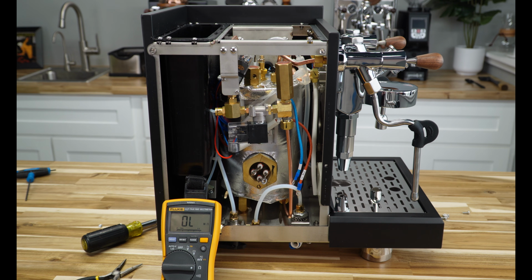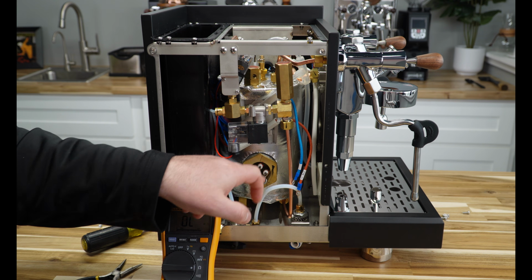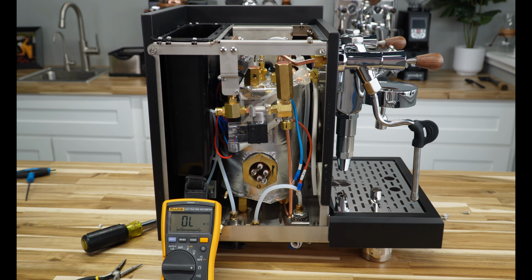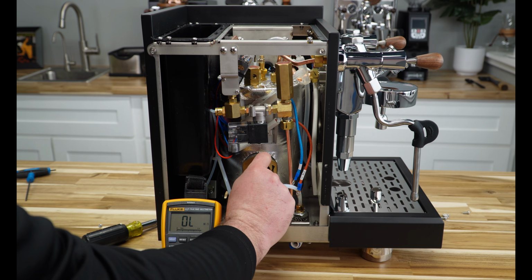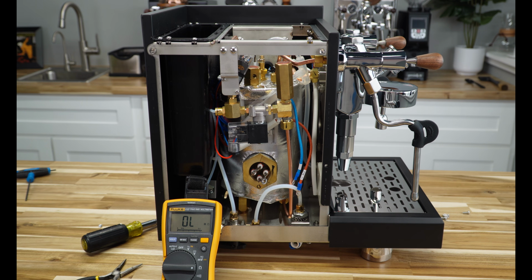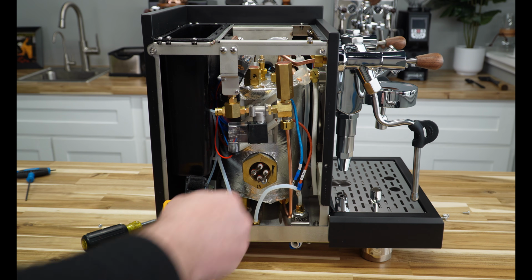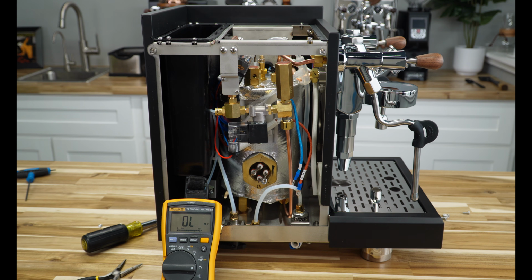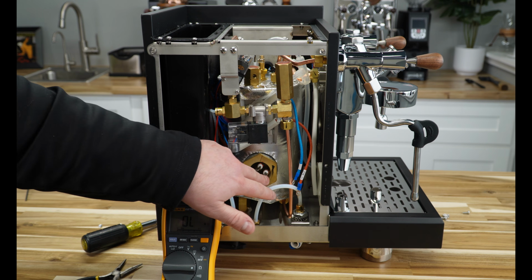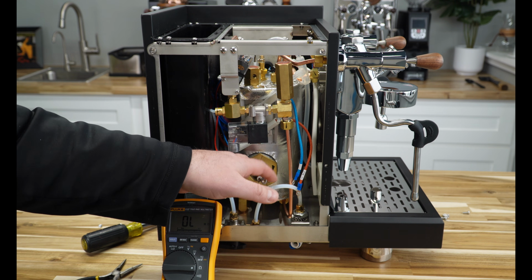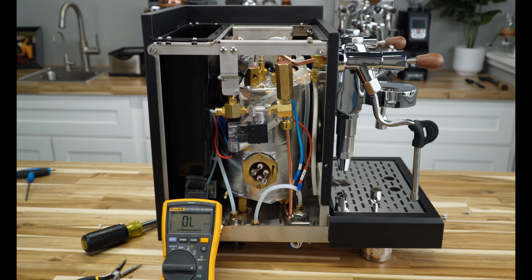You'll notice this actually has two heating elements built into one unit, so this is a loop and this is also a loop. You might have just one side damaged, and in that case you'd have to replace the whole heating element, so it's not the end of the world. Some machines have individual heating elements you can separate out the wiring for, but this one has them welded together, so you can't test them individually. Either way, if they're bad you're replacing the whole heating element anyway.